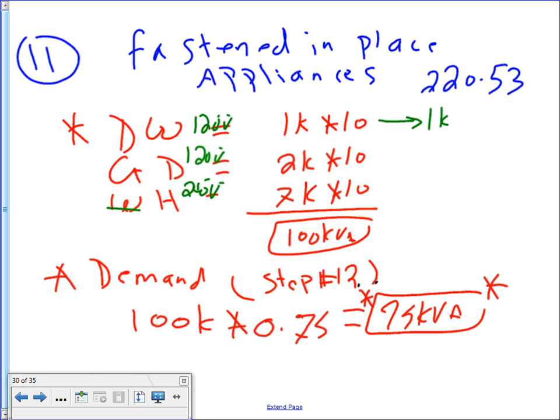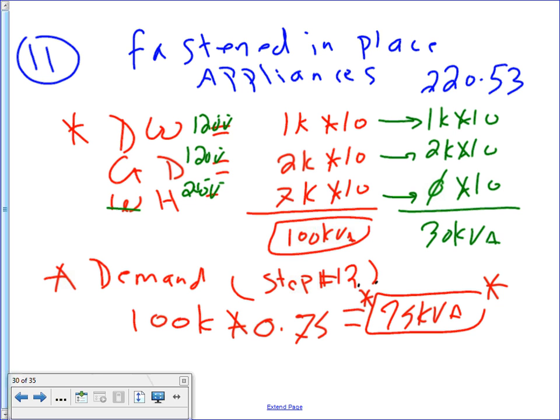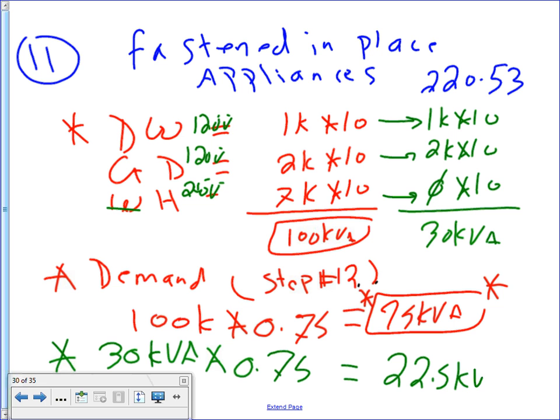There is 1K times 10 for the neutral. This is 2K times 10 for the neutral. Since for the neutral it is going to be 0, because why 0? It's a 240 load. Times 10. When you add them up, you're going to end up with 30 kVA. And then you apply the demand factor here. You take the 30 kVA, multiply it by the same thing, 0.75. That will get you a healthy 22.5 kVA. Ladies and gentlemen, this is what you need to carry.